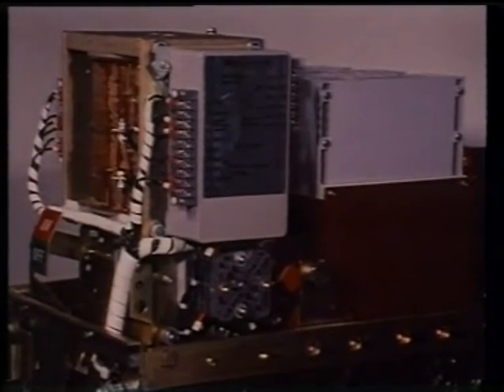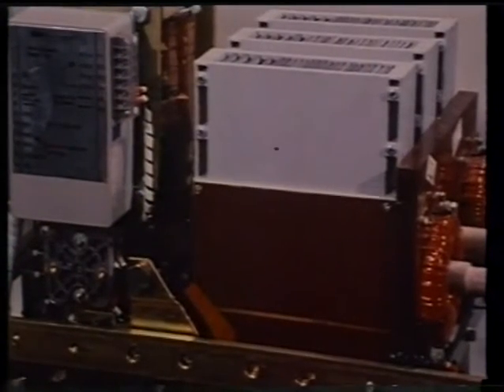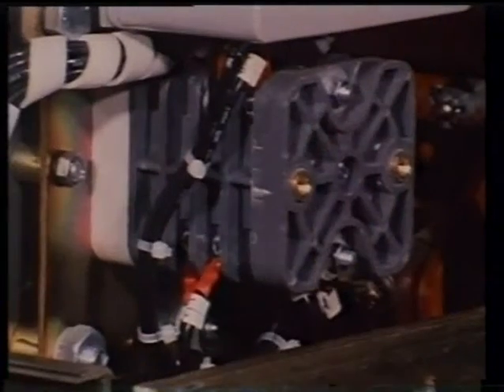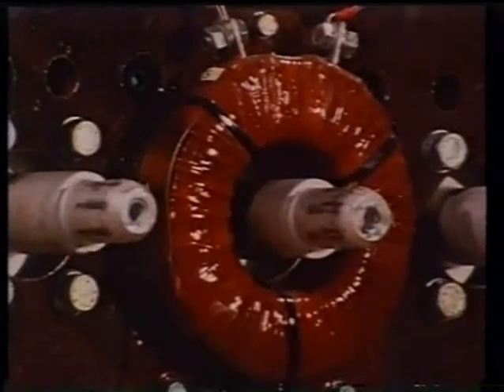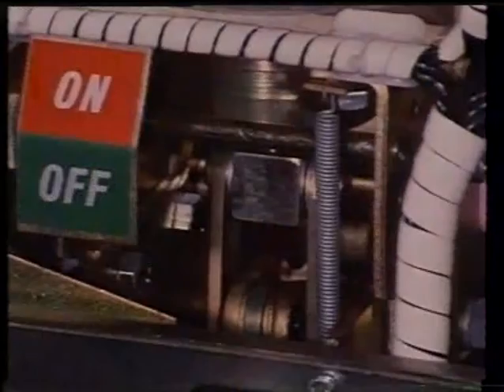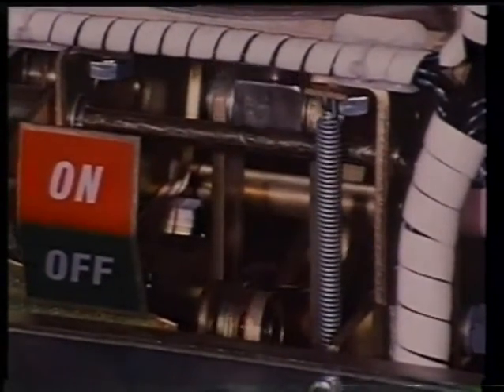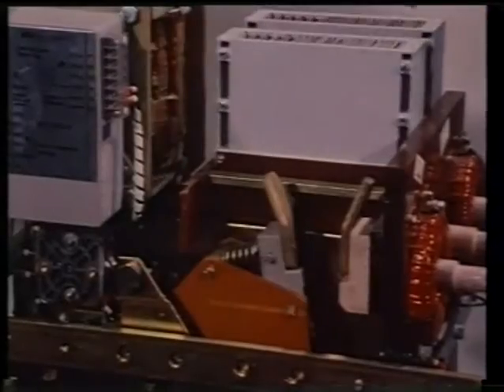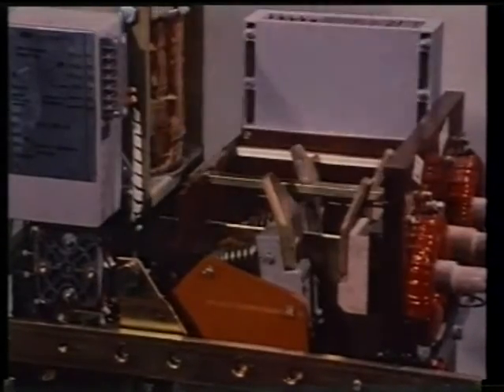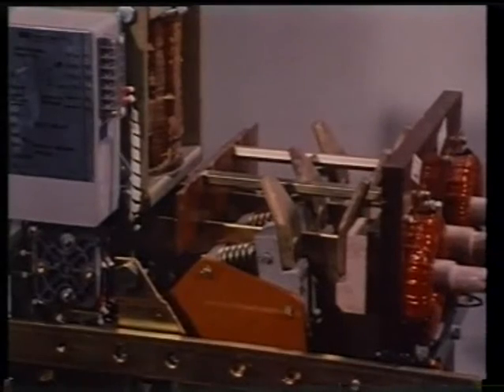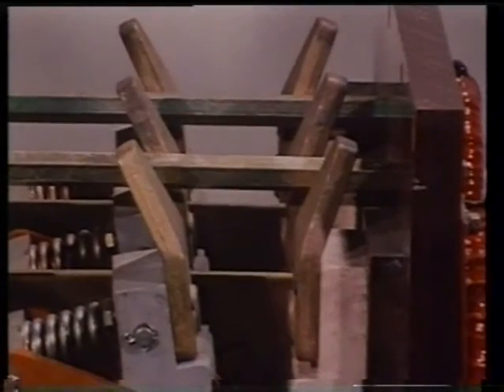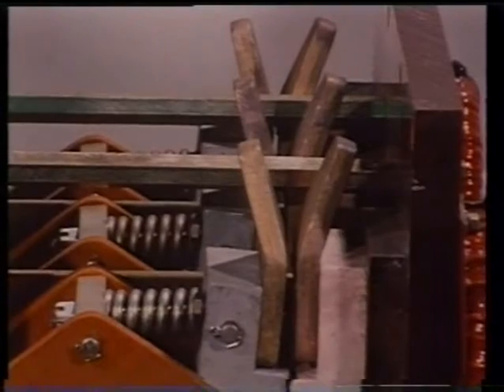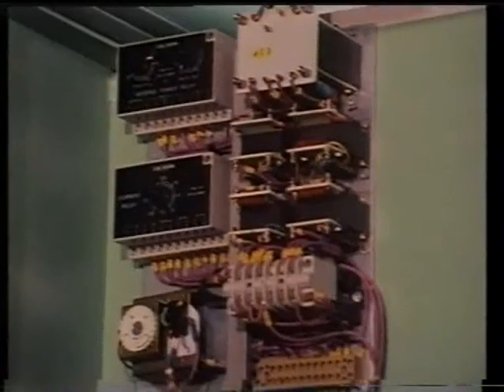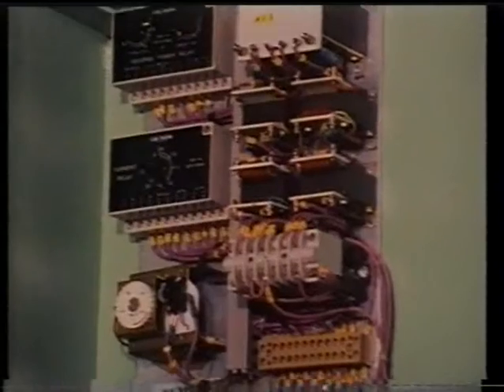Check that all circuit breakers will pass a visual test, paying particular attention to the condition of main, arcing and auxiliary contacts. All internal wiring must be sound and the mechanical linkages free of wear and stress. Arc chutes must be clean, free of arc debris and correctly aligned. Look for signs of wear, misalignment or overheating. Check the reverse power relay and the preferential trip relay for correct timing and operation. Consult the ship's manual for correct settings.